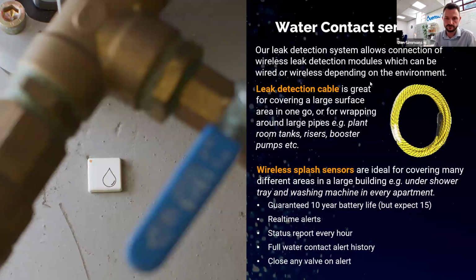As well as flow monitoring, we do very simple leak detection cables and splash sensors, which are a bit like fire alarms - if water comes into contact with them, they will just shut the water off. These are for very high-risk areas like server rooms or drip trays, and they can all be integrated or self-contained as well.